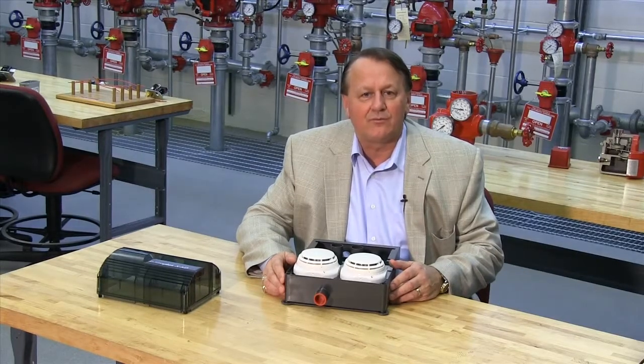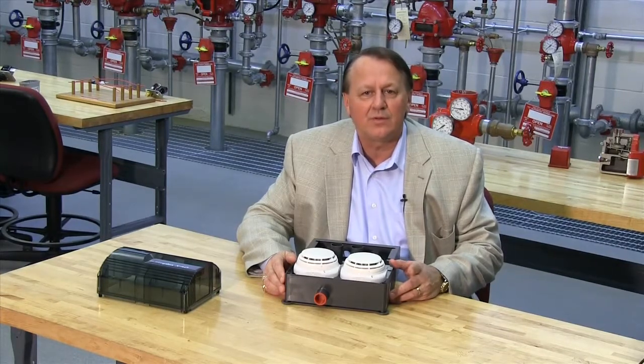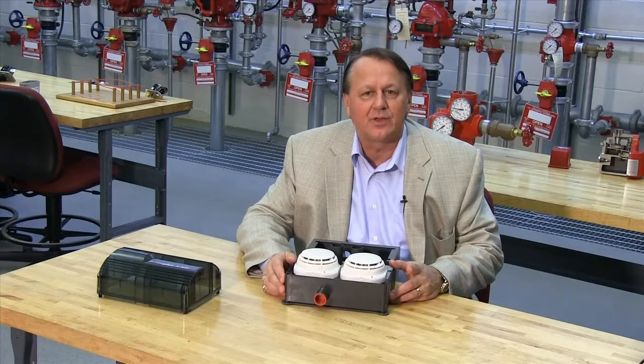For commissioning or verification of the installation, the unit can also be tested with a magnet. Remember, this will only test the electronics of the device and make sure they are functioning and is not a substitute for the annual NFPA functional smoke test.